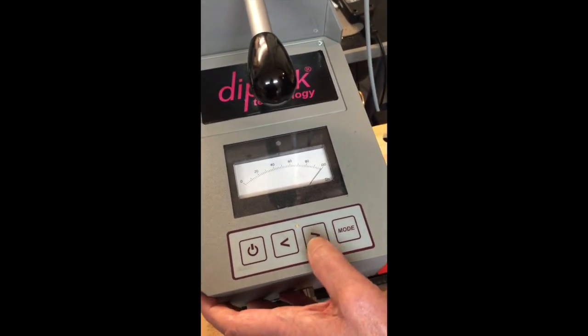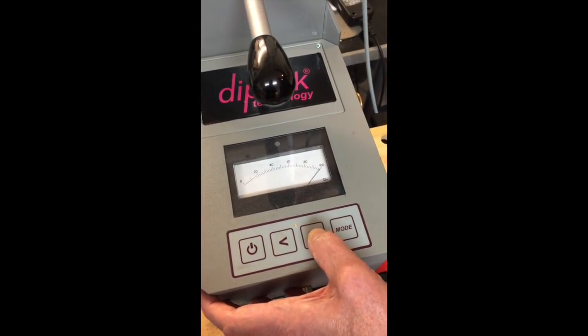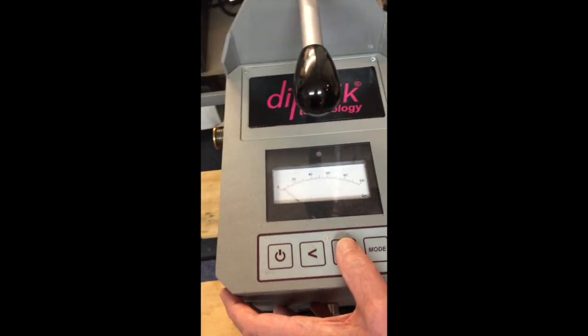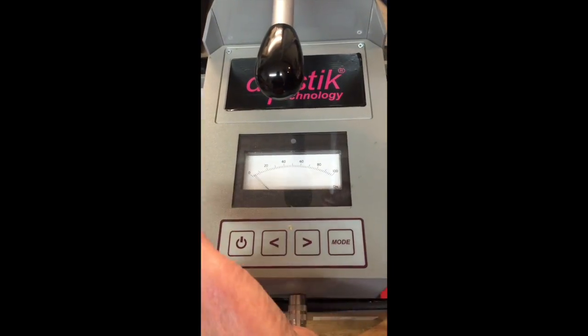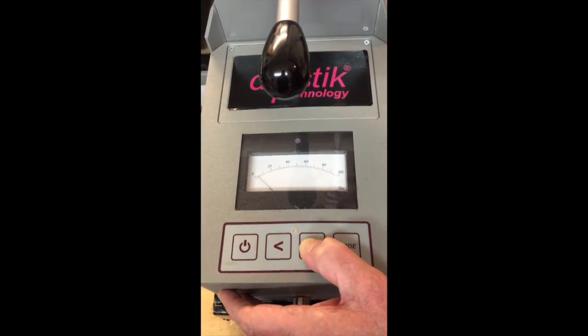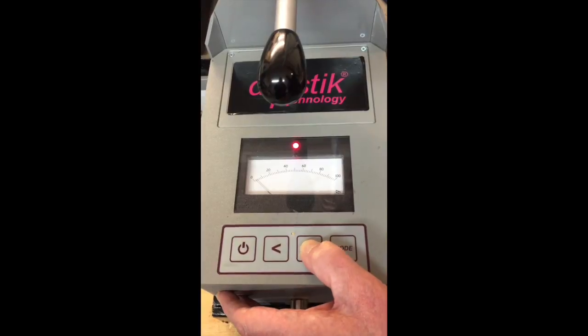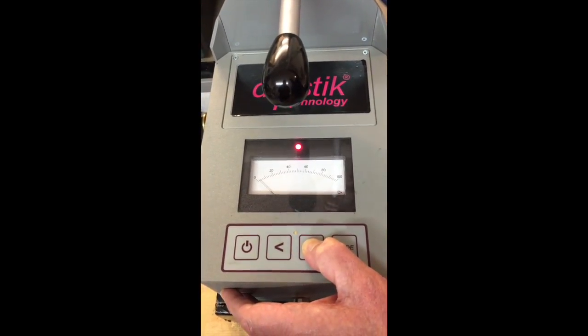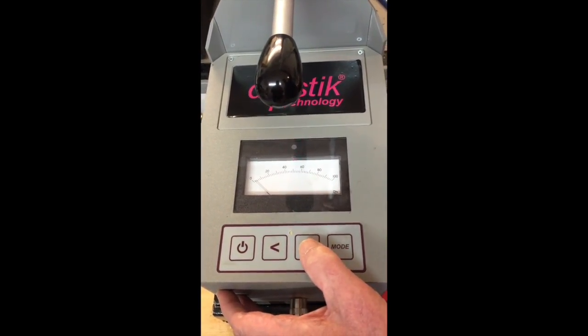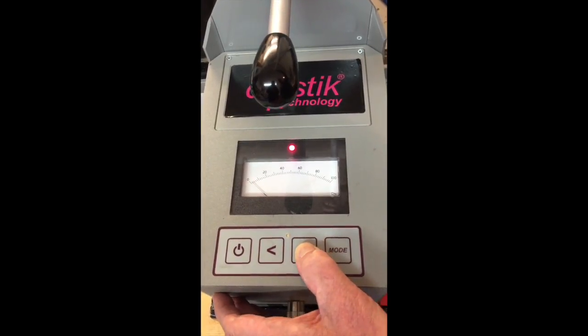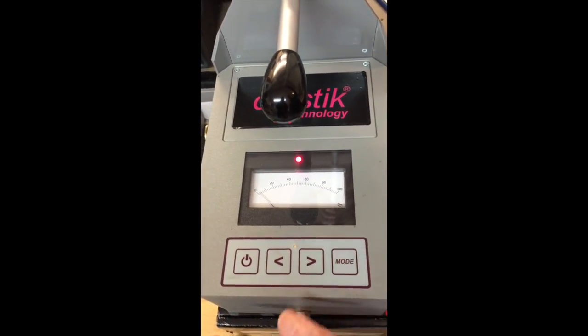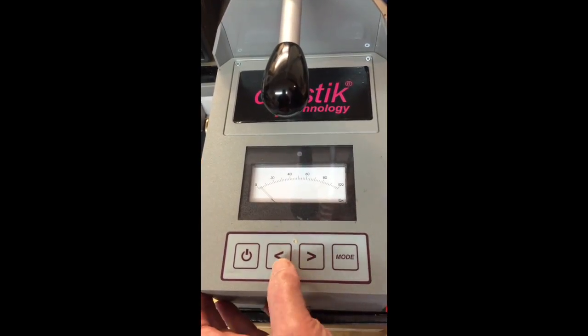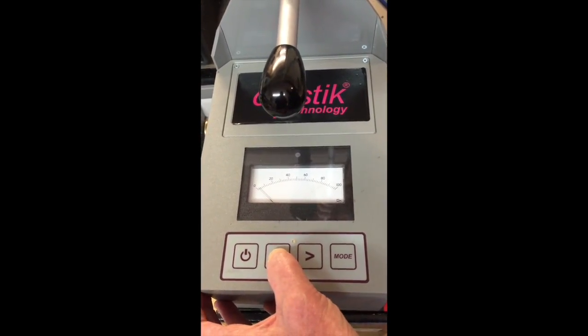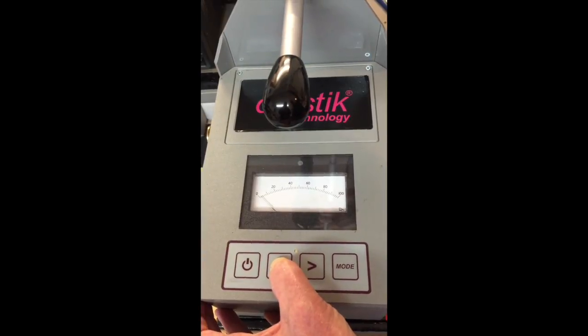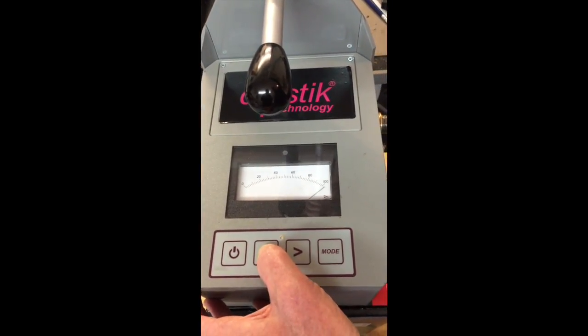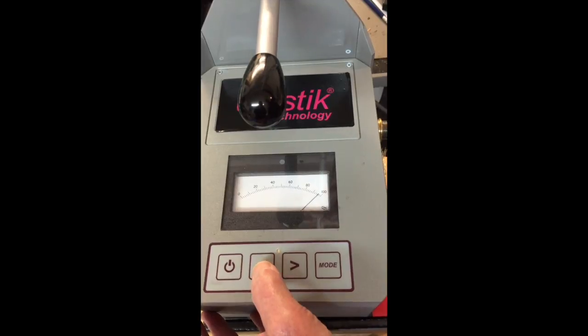Go for it, Bob. Yes, because it's possible to keep on, supposing for instance that you wound too far and you've got 0, to try and increase you use the up button, and nothing happens. What does the light indicate, Bob? The light is now lit to show that you've reached the end stop for the travel. So using this key, what does that indicate you should be doing? You should now change and start using the down key. But nothing's happening. Ah, then as you keep going you will come back into the measurement range.